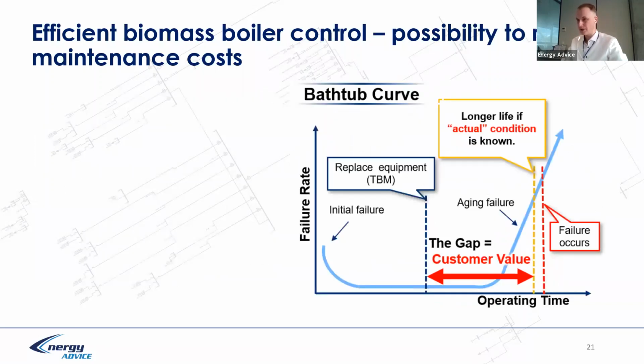Okay, coming back to bathtub curve. You remember from the university time that failure rate is high at the start of operation of a boiler. During operation, probably failure rate could be lower, and failure rate increases at the end of operation time. So, in fact, our decision to do maintenance or to replace something could be too early or too late. Too late, it's not good because we stop boiler. Too early, it costs. So in fact, we balance in between here. If we move this curve to the right, it increases risks, but saves money, probably due to maintenance, but increases risk and probably it could cost. If we do it earlier, this also costs.